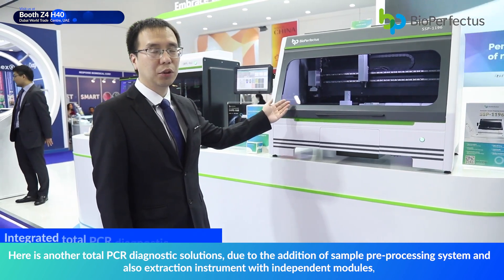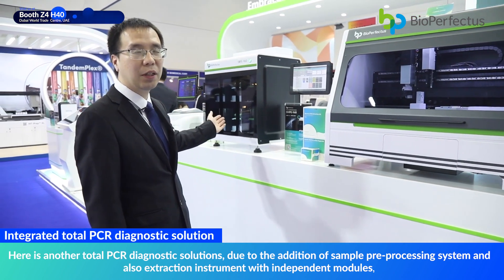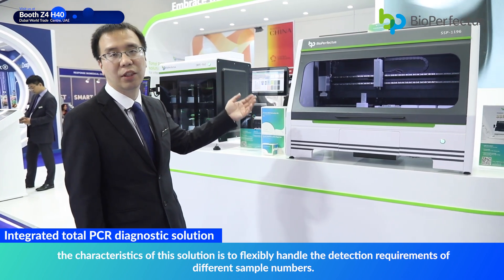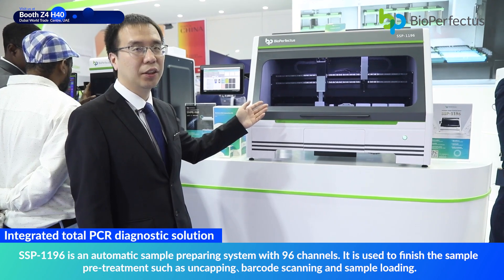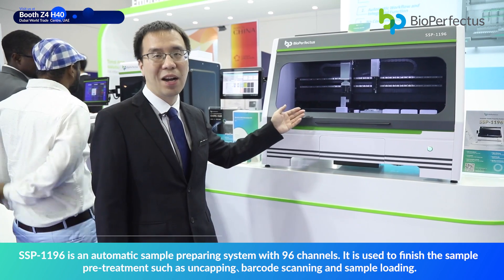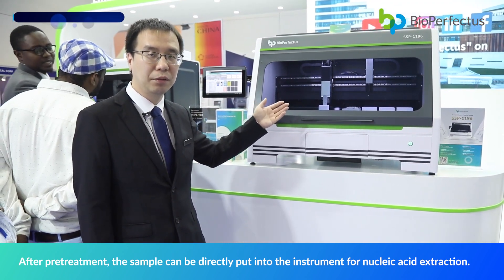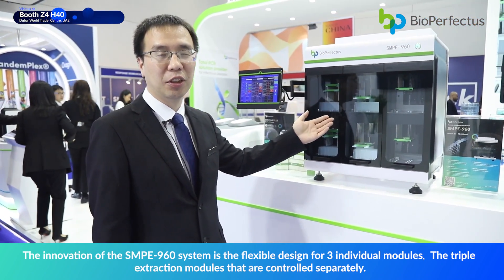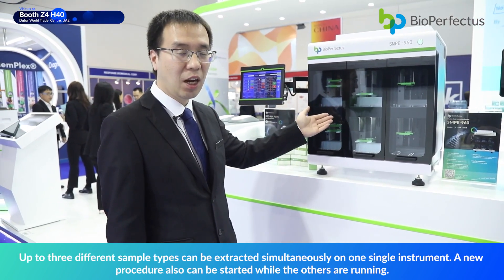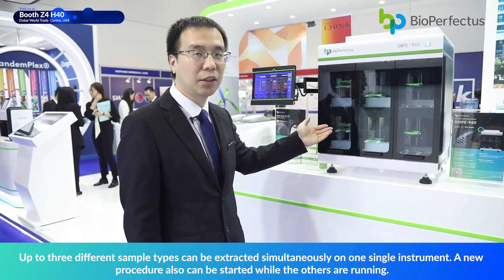Here is another total PCR diagnostic solution featuring a sample pre-processing system and extraction instrument with independent modules. The characteristic of this solution is its flexibility in handling detection requirements for different sample numbers. SSP-1196 is an automatic sample preparing system with 96 channels, used to finish pre-treatment such as uncapping, barcode scanning, and sample loading. After pre-treatment, samples can be directly placed into the instrument for nucleic acid extraction. The SMPE-960 system features a flexible design with three individual modules — triple extraction modules controlled separately — allowing up to three different sample types to be extracted simultaneously in one instrument, and new procedures can be loaded while others are running.